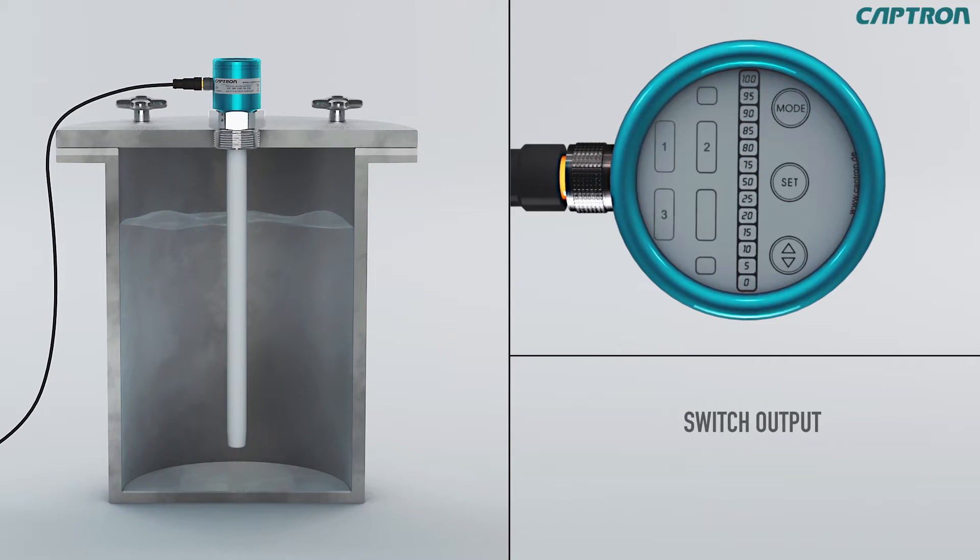Setting the switch output PNP1. The 0 and 100% displays will light up once again, as well as the NO or NC display for PNP1. NO stands for normally open, and NC for normally closed contact. You can set NO or NC with the up down button. Confirm your adjustment with set.